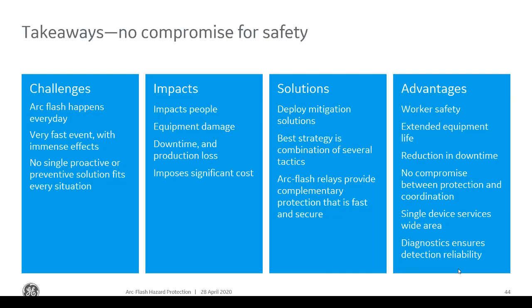How do light sensing inputs affect the incident energy during active maintenance? So the light sensor does reduce the arc flash levels, because you are reducing the trip time. Trip time equals arc flash energy, right? So you are reducing the arc flash energy using the light sensor. It is intended for equipment protection as well as personnel protection, to protect maintenance personnel. One of the main reasons for using light sensors is probably personnel protection, because you're not really gaining much more otherwise versus a low impedance bus differential.